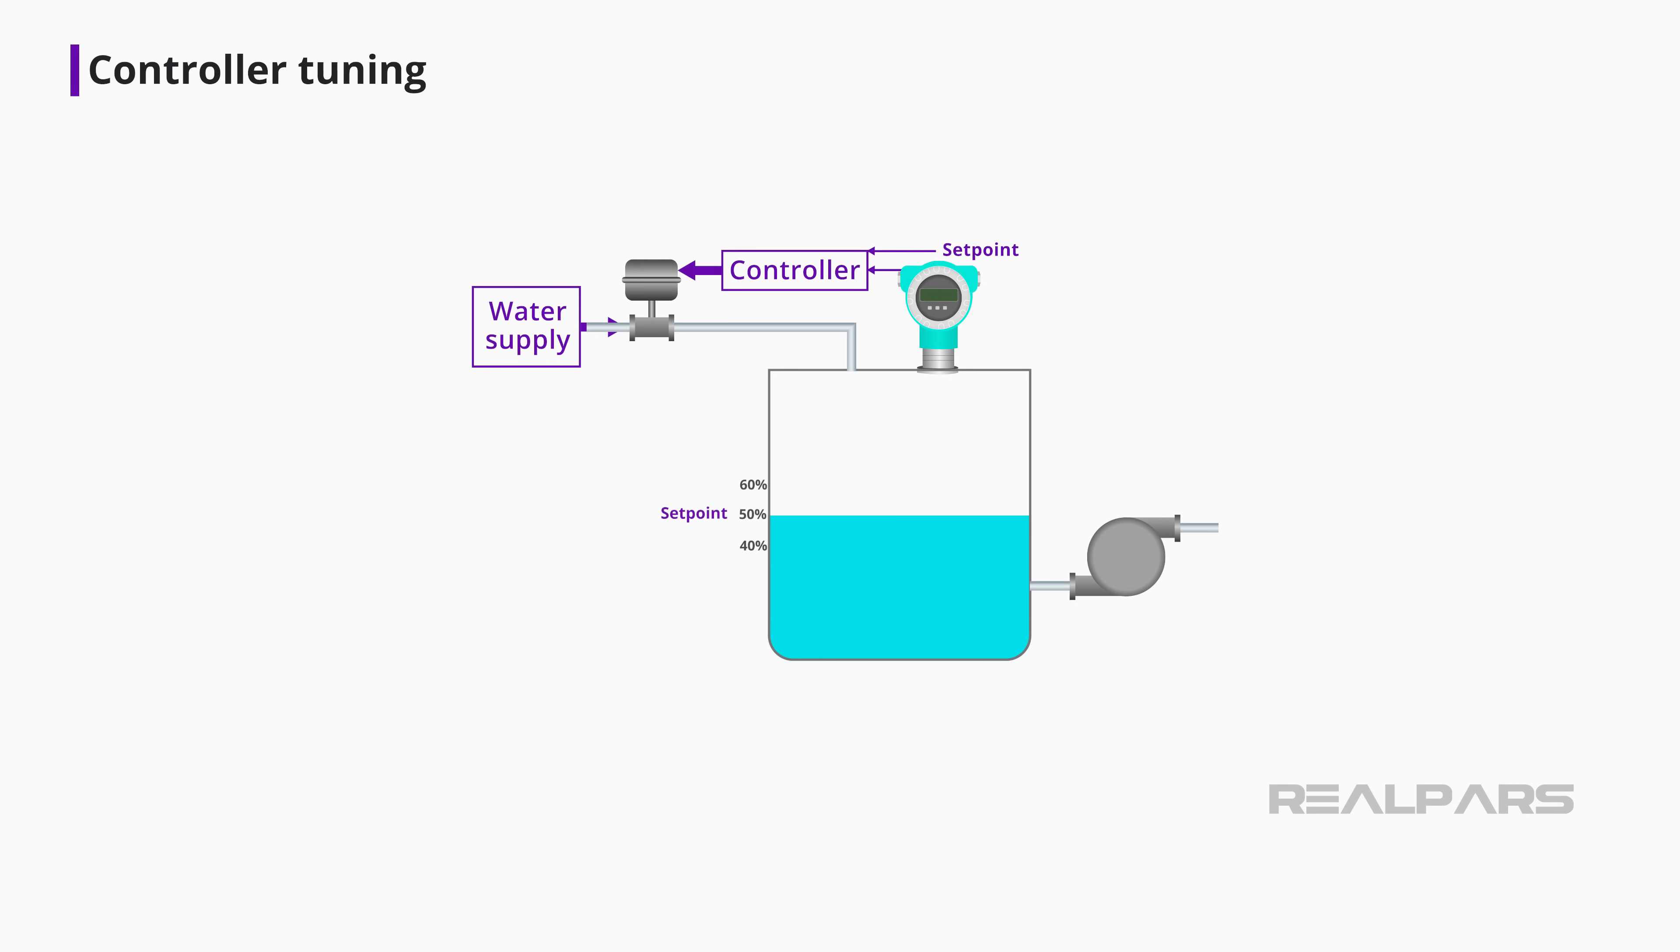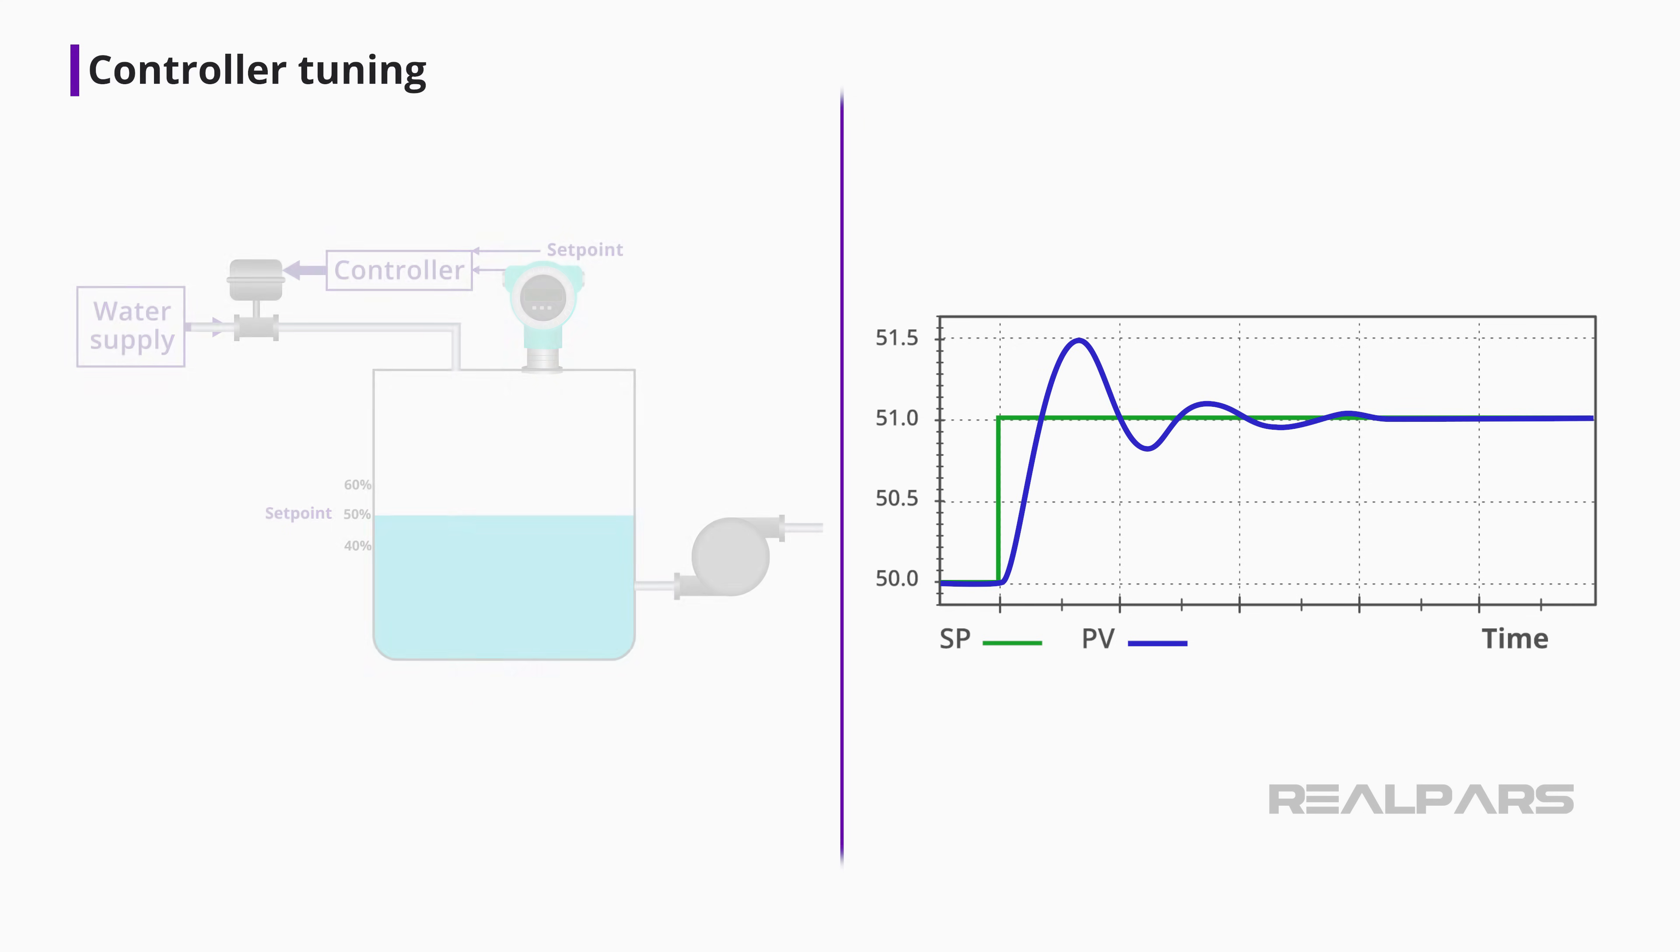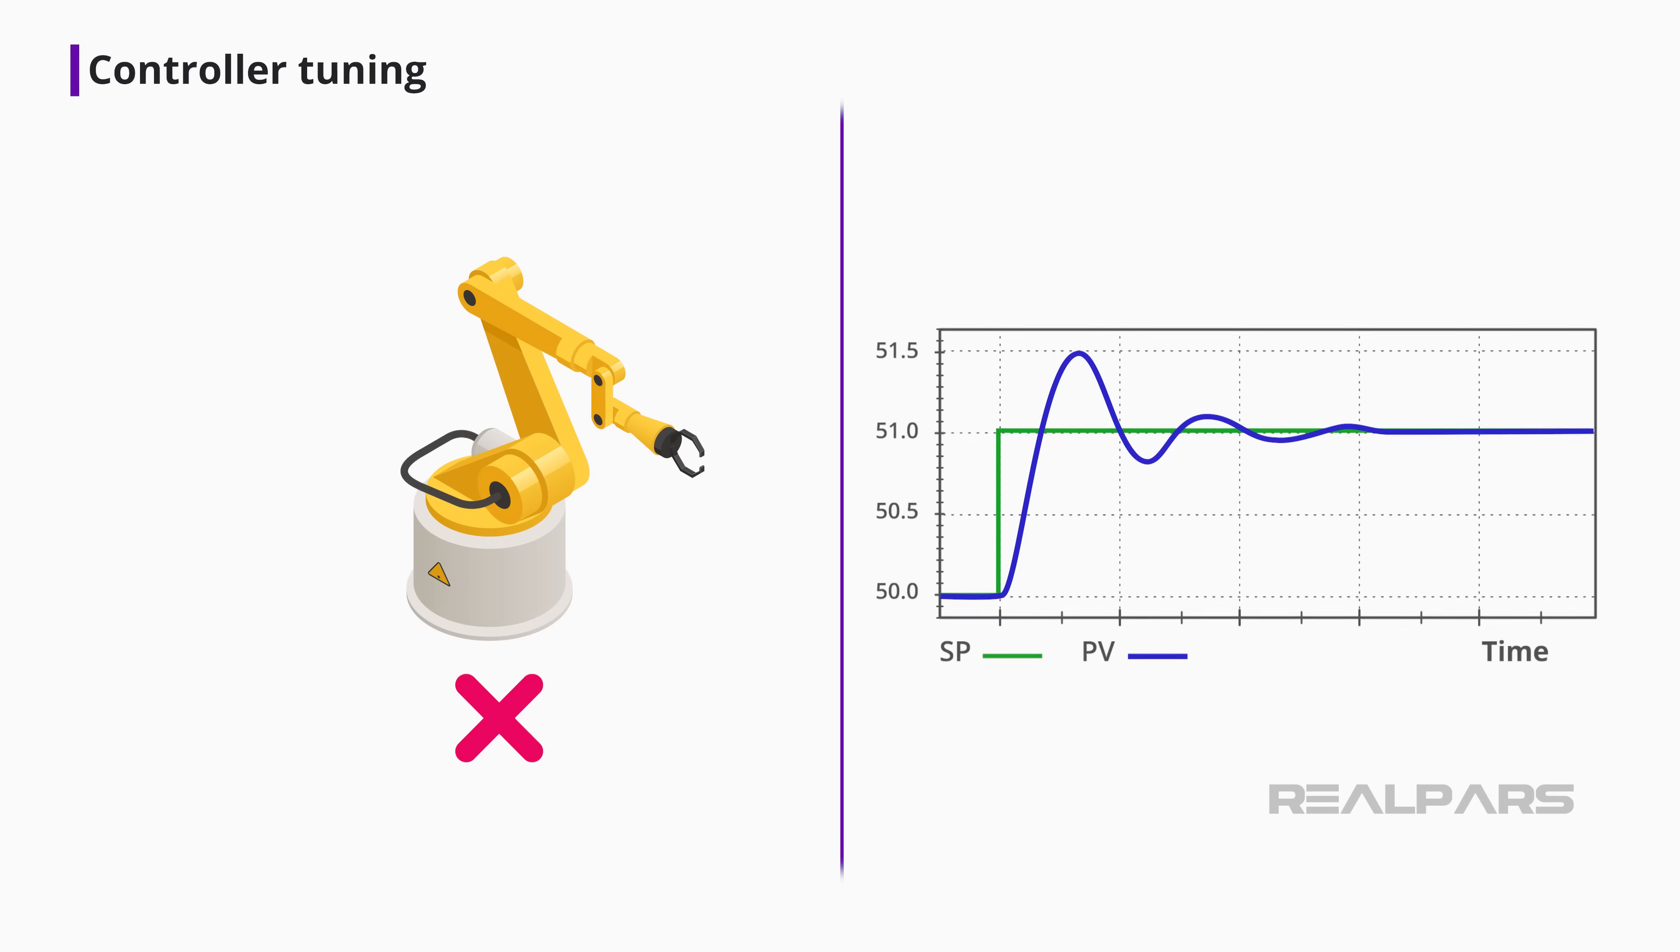For example, after the controller has been tuned, a setpoint bump of 1% in a tank level control produces a quarter-wave damped response. This type of response may be suitable in a tank level process, but could be disastrous in a motion control process.